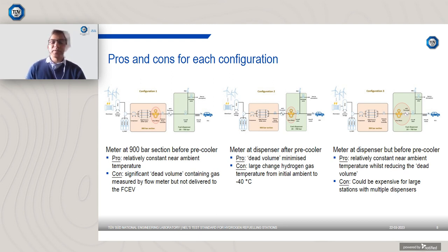As a result of the issues with configuration number 1 and number 2, some hydrogen refueling stations recently have gone with a system where they have installed both the flow meter and the pre-cool or heat exchanger inside the dispenser unit. This way, the flow meter sees a relatively constant temperature and at the same time the dead volume is minimized. There are a couple of issues with this setup, though. One is that you need to have individual heat exchangers installed for every single dispenser, which could be expensive. The other issue is that the footprint area for the dispenser would therefore increase, which may limit the number of dispensers that you could install at a refueling station.